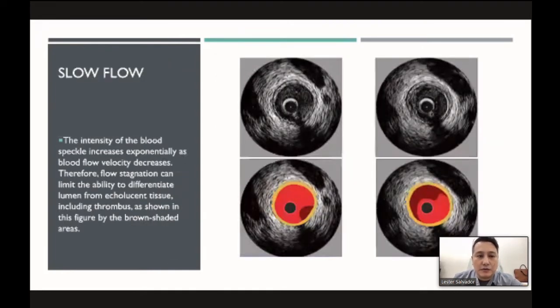Another artifact is slow flow, where the intensity of the blood speckle increases exponentially as the blood flow velocity decreases. So when there's flow stagnation, it is often most evident when the catheter is advanced across a tight stenosis. This can limit the ability to differentiate the lumen from echolucent tissue, including the subplaque, the intima, or the thrombus. In this situation, flushing of the vessel with saline or contrast is particularly helpful for differentiating the lumen and the vessel wall.